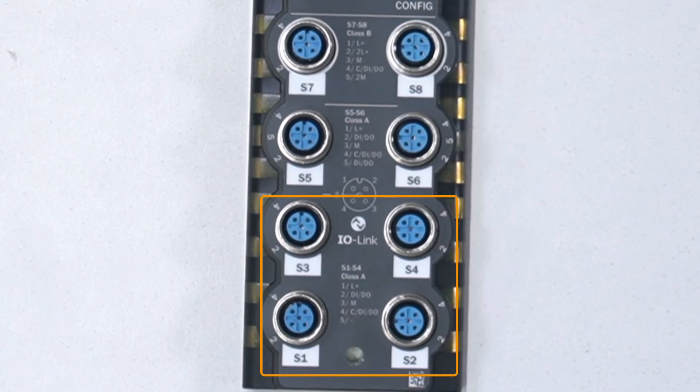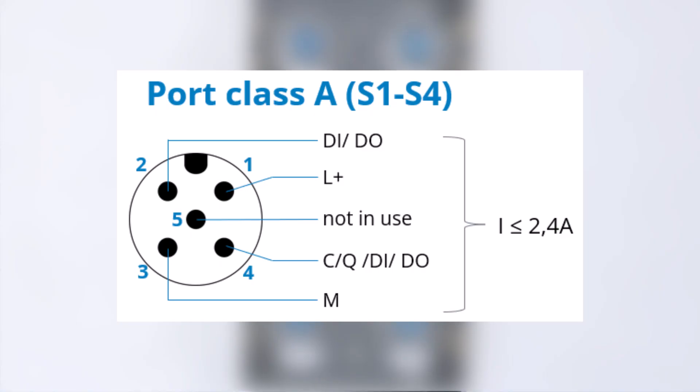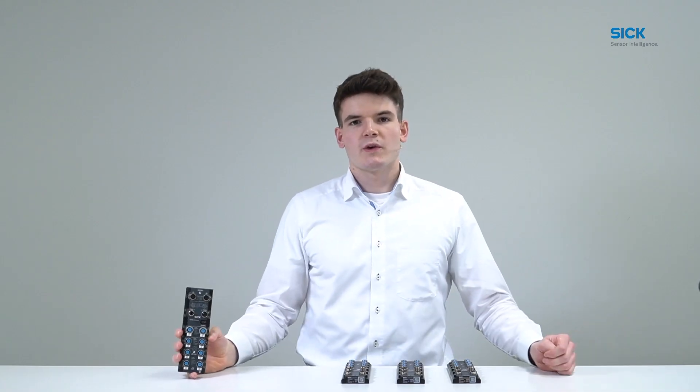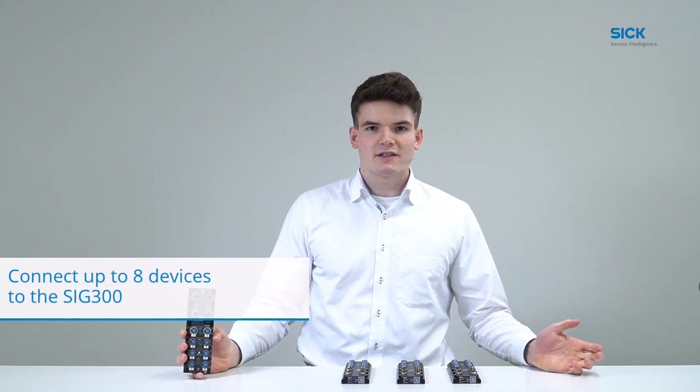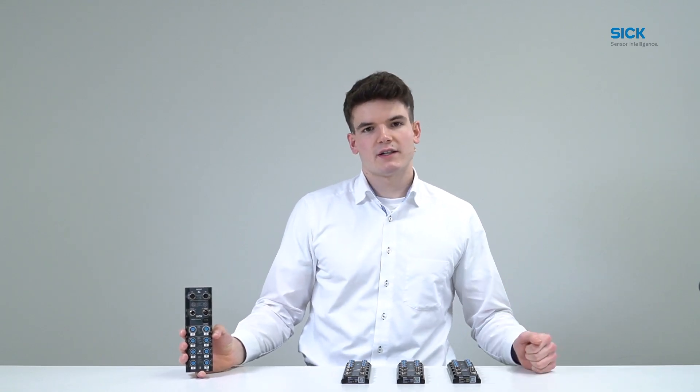Ports S1 to S4 are 5-pin class A ports. Pin 1 and 3 are used for the power supply. Pin 4 can be used as a digital input or output or for IO-Link communication. Pin 2 can also be used as a digital input or output, and pin 5 is not in use. Therefore, ports S1 to S4 can be configured as a maximum of two digital inputs or outputs each. So in total, we can connect up to 8 IO-Link devices to the SIG300 with 8 digital inputs or outputs, or 16 digital inputs or outputs if no IO-Link devices are connected.